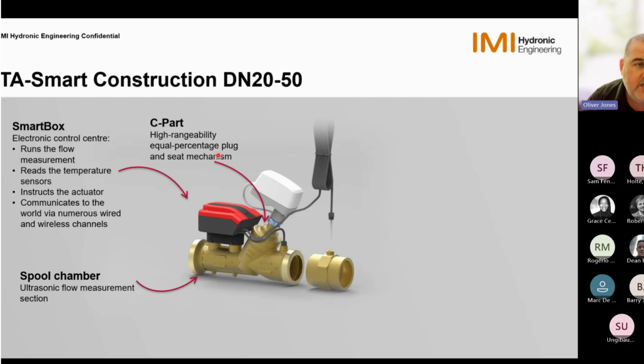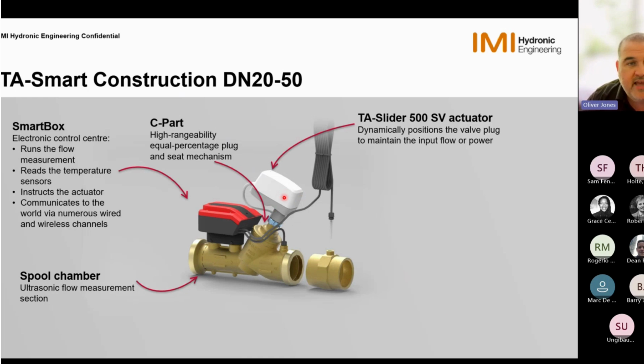We then have the C part, which is our high rangeability, so we can control down to very low flows. Equal percentage plug and seat mechanism, so this is what's giving us that characteristic curve that we saw on screen earlier. And then on top of that is mounted our TA Slider 500 smart valve actuator, or SV actuator, which dynamically positions the valve to maintain our input flow or power.